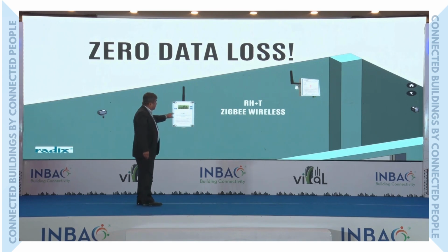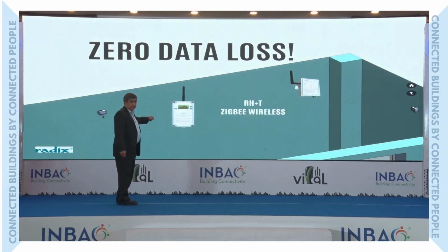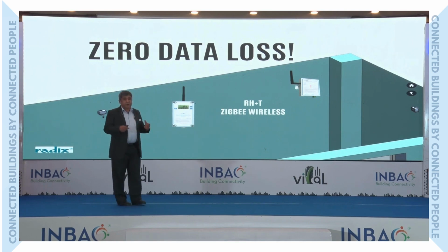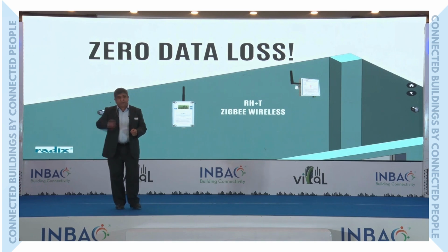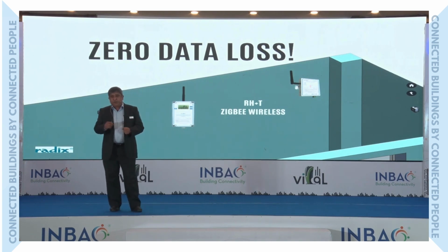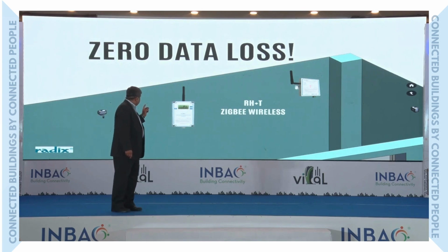This transmitter and that receiver that you see over there, they've got data logging in it. It saves data for a period of 16 days. So if the network fails, the first thing the unit will do, since it's based on a mesh network, is look for the next device, and it hops on to the next one. If that device is not available, the data will be stored in the unit for 16 days, and when the network comes back, it sends the data out again. The receiver also has data logging facility, making sure that your data is never ever lost.